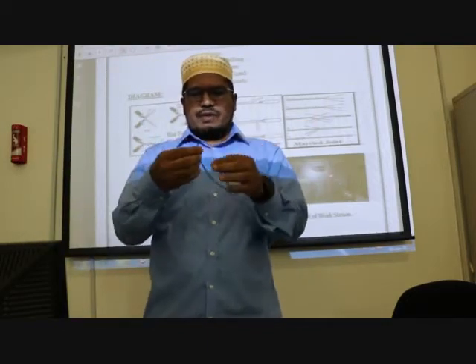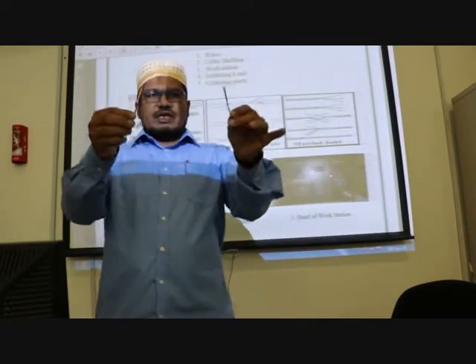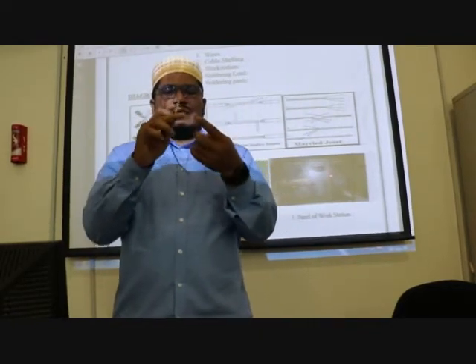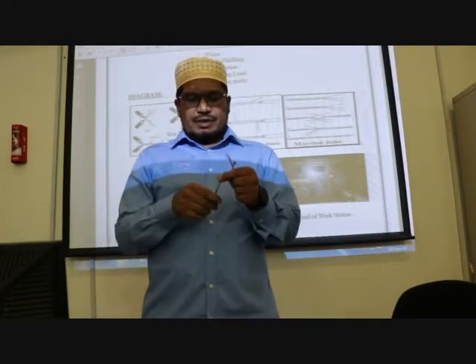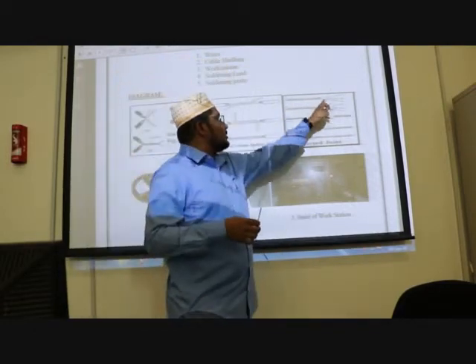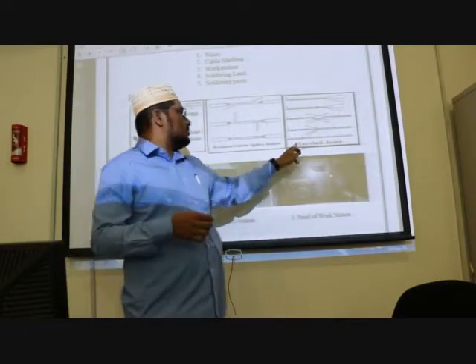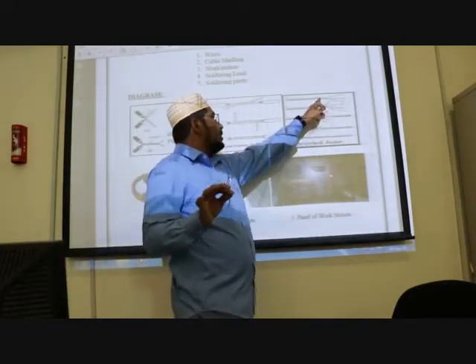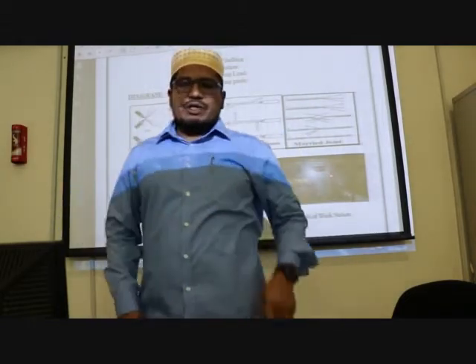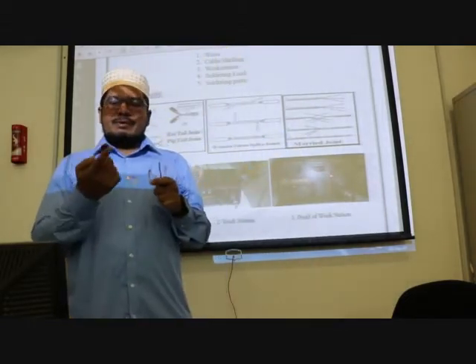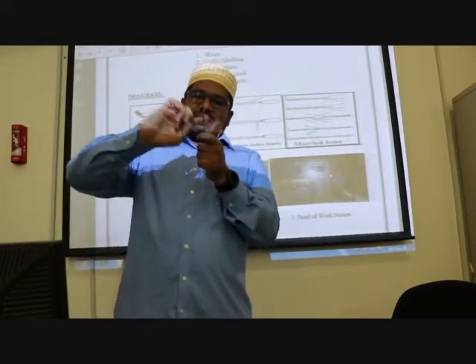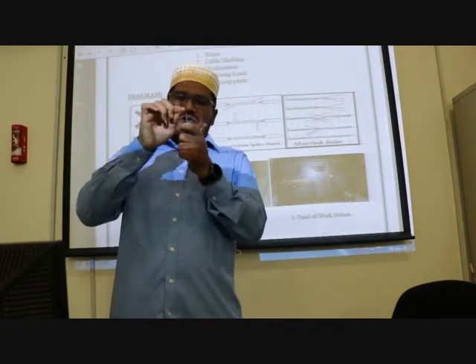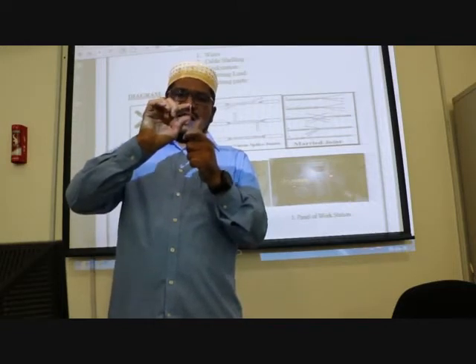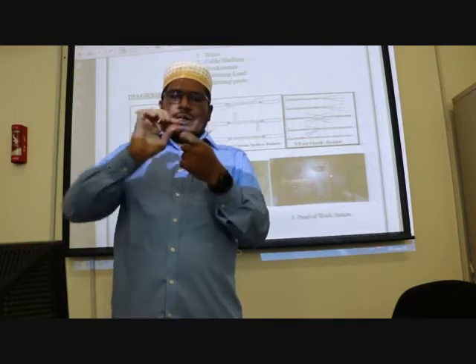Now we have 2 wires. In practice these would be big wires, but I am using a small part of the wire for demonstration. So these are the 2 wires with 2 inches of insulation removed, and they look like this. As I told you, the Western Union splice joint and married joint both have the same procedure for making. Now what is the next step? After removing the 2 inches of insulation from the wire, in this 2 inches or whatever size, half of the conductor strands, from the bottom, you have to make it tight. See, you have to make it tight.